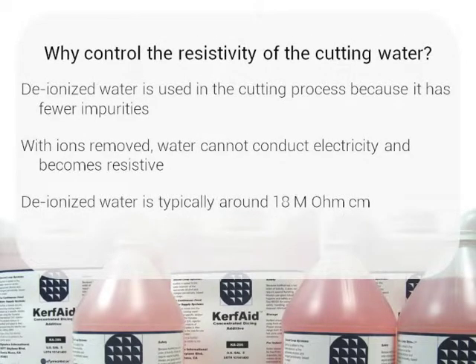Why control the resistivity of the cutting water? Water used in the wafer dicing process is typically deionized to remove the impurities found in city water. By definition, water that has been deionized has had its ions removed. Without these ions, water cannot conduct electricity and becomes highly resistive. Deionized water used in wafer dicing is typically around 18 megaohm centimeters.